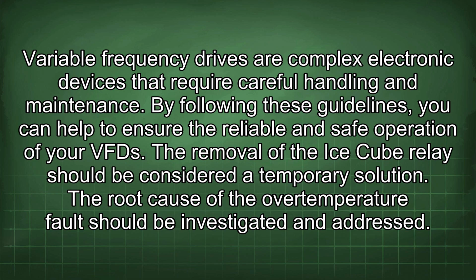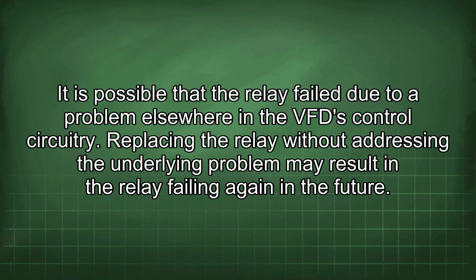The removal of the ice cube relay should be considered a temporary solution. The root cause of the overtemperature fault should be investigated and addressed. It is possible that the relay failed due to a problem elsewhere in the VFD control circuitry.